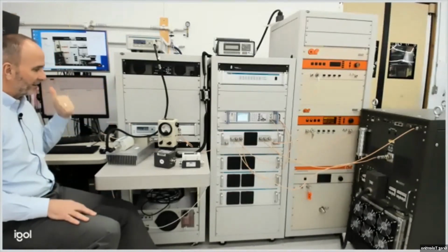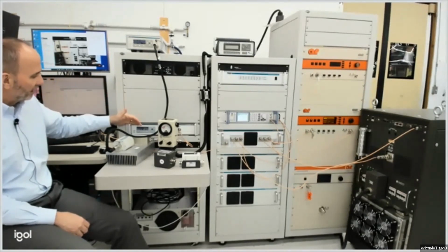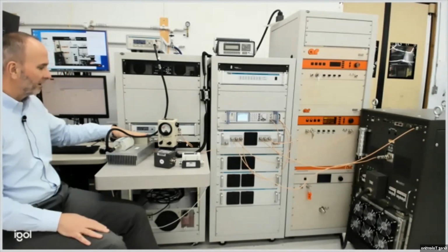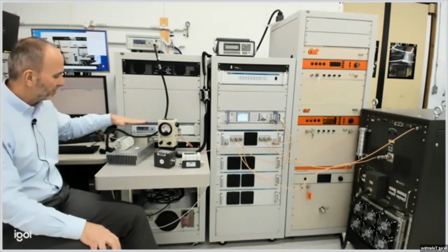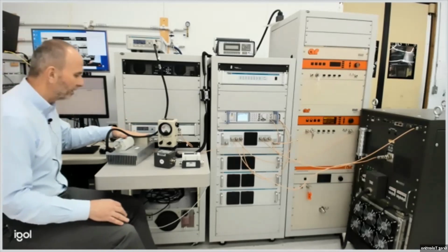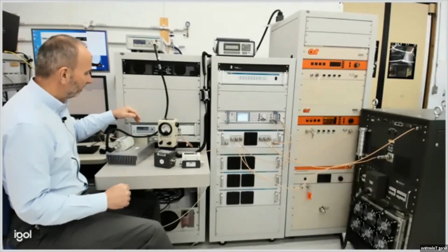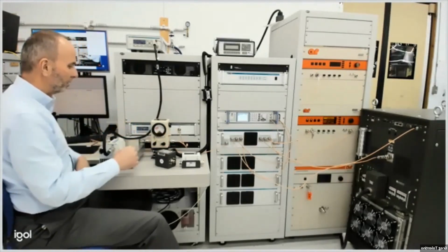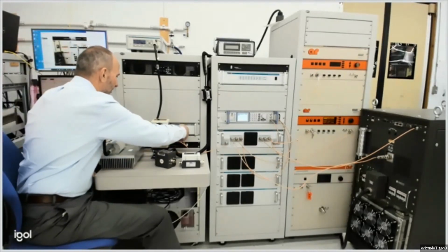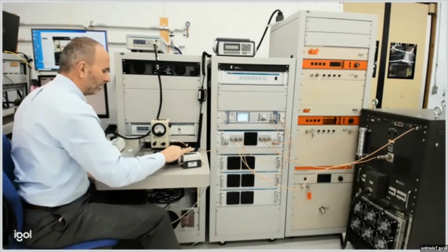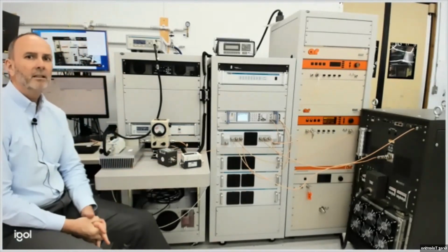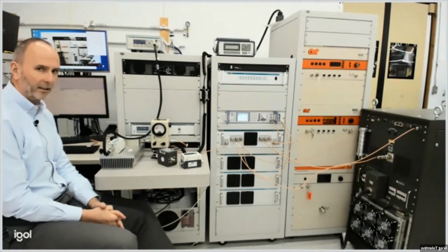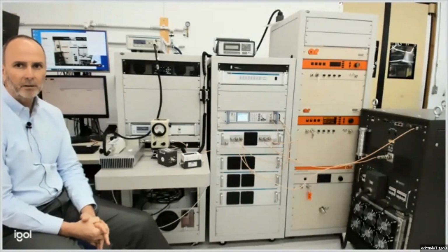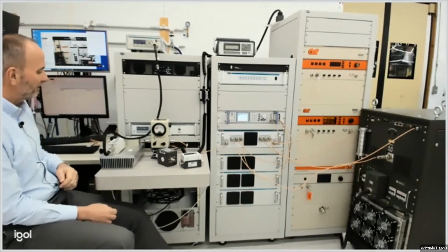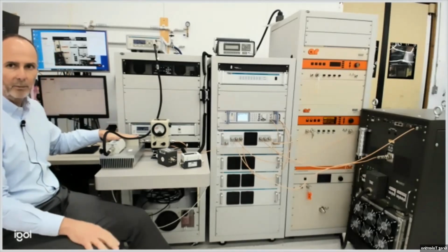This software, the HPCSW that I showed you, has a routine for using the calorimeter to calibrate a transfer standard. So I was in fast cal mode today, which uses a transfer standard. In regular mode, I could have put the device under test right onto the input of the calorimeter, right there, and done a more time-consuming but lower uncertainty calibration using the calorimeter driven by HPCSW. Then HPCSW actually was used to create the coupler calibration factors that we imported today.